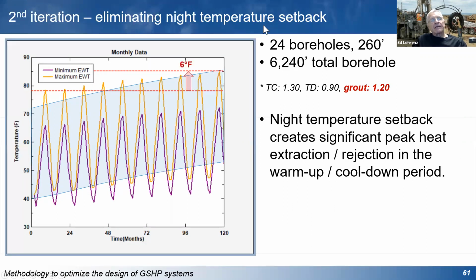If we eliminate the night setback, and this is where working with the building operator on how they run the building comes in, there's a fairly large perception, and some of the controls manufacturers have really promoted the use of night setback to reduce energy consumption. And in reality, it doesn't help reduce energy consumption very much, but it does make a difference on how much heating and cooling capacity you need to supply to that building. For example, if you start up the building from a 10 or 15 degree night setback, first thing in the morning you're going to need a lot of extra capacity to run for a couple of hours to start warming up the building, and the mass of the building, all the furniture and everything else in the building has to be warmed up. So it takes a lot of energy to do that.